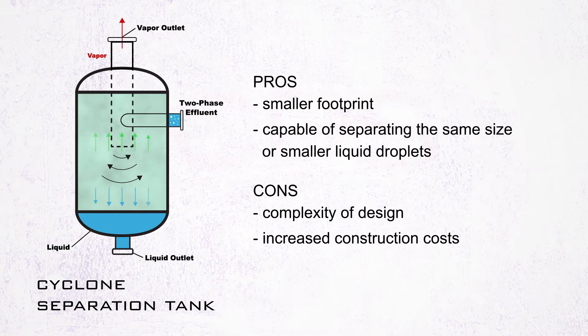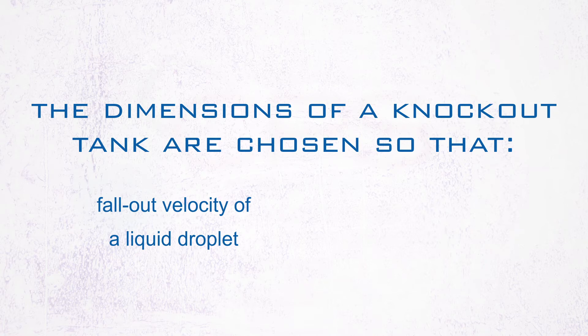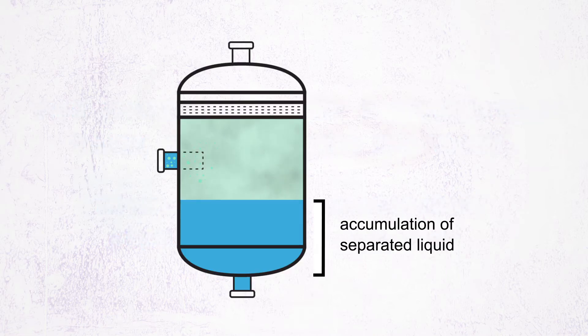Regardless of the type, the dimensions of a knockout tank are chosen so that the fallout velocity of a liquid droplet is greater than the superficial velocity of the vapor, while providing enough volume for accumulation of the separated liquid.